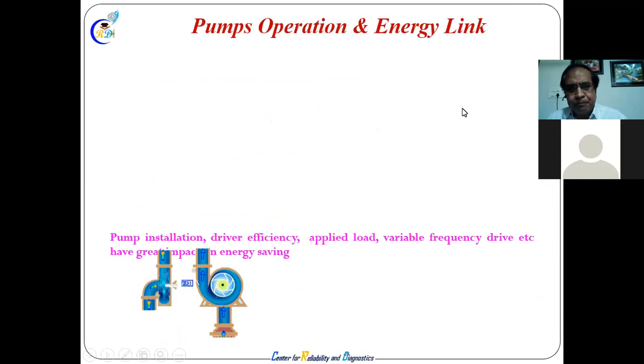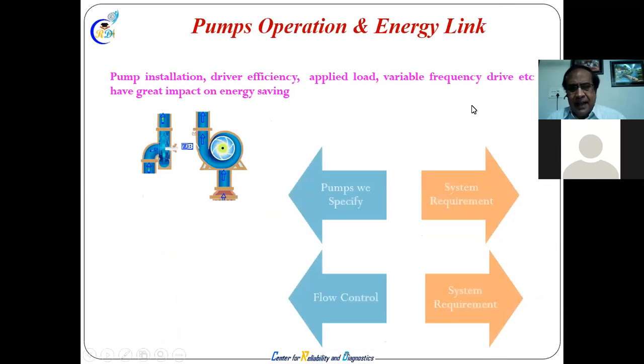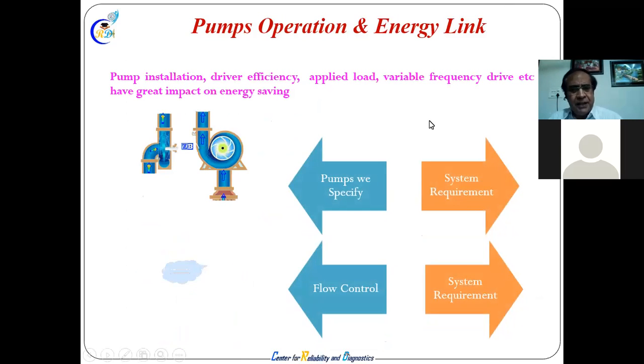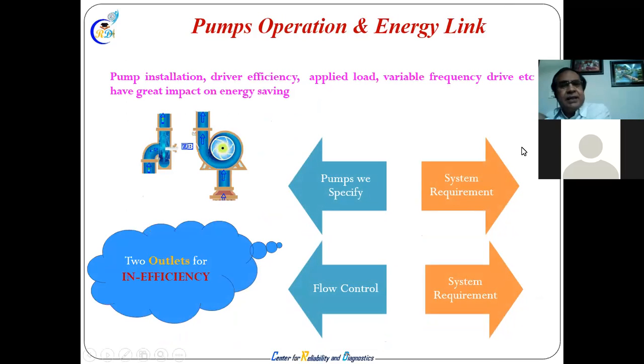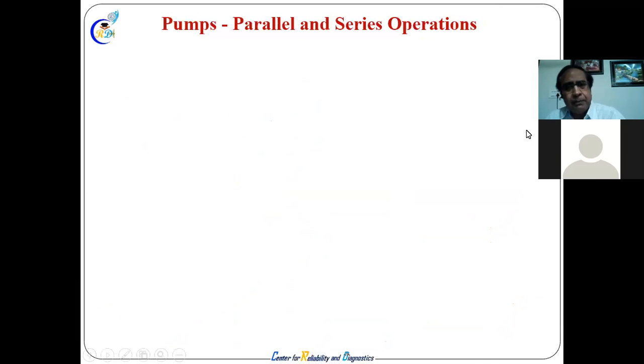So for energy saving, there is a lot of linkage. The pumps we specify are important, and the system requirement is important for better efficiency. So these are the most inefficient ways. Either flow control takes out our efficiency, or the pumps we specify are not at the system requirement. So this is the problem.